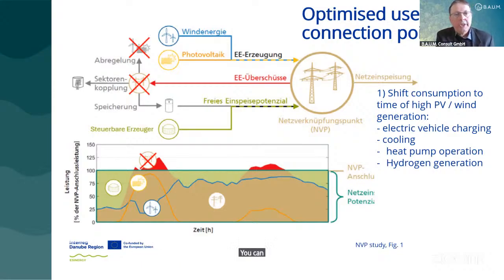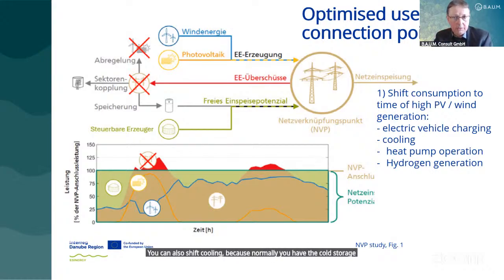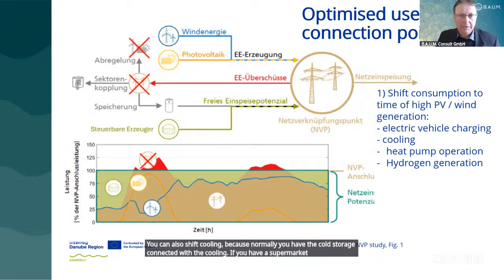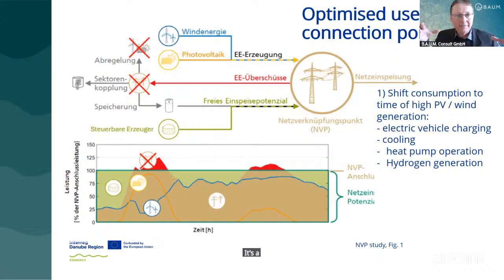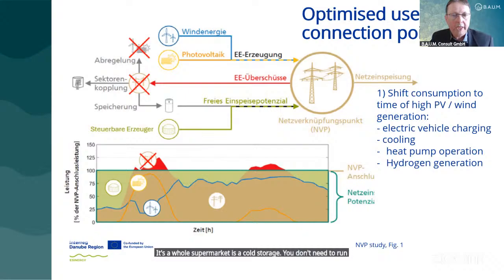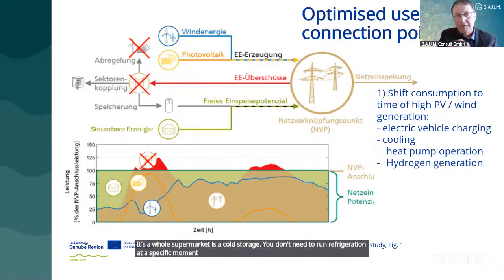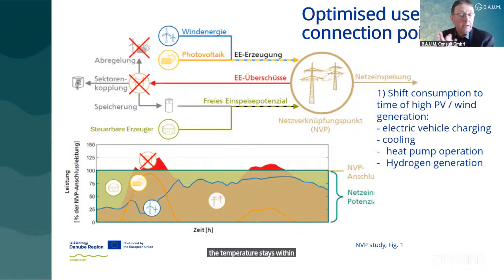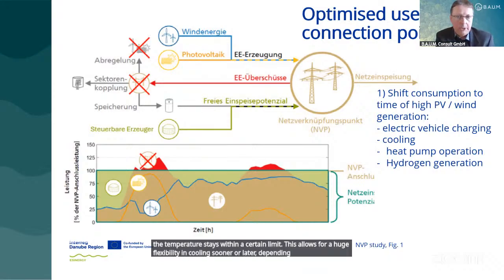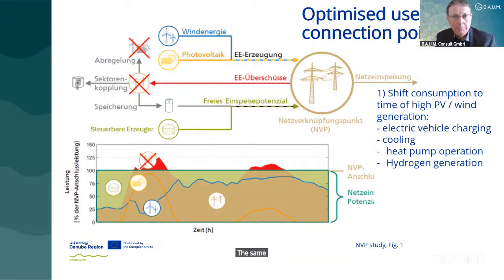You can also shift cooling, because normally you have a cold storage connected to the cooling. If a supermarket is cooled, the whole supermarket is a cold storage. You don't need to run refrigeration at a specific moment, but just ensure the temperature stays within a certain limit. This allows huge flexibility in cooling sooner or later, depending on the availability of renewable electricity. The same applies for heat pump operation.